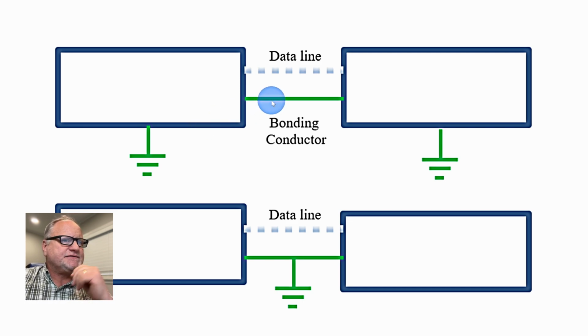It sounds great. Let's take out this bonding conductor here first. Act like this is not here. If you have this scenario, first of all, this common ground is going to be in this rack, because the things you have plugged into the house power, on that third prong of the three prongs, are going to be the common ground to the building. So you're going to have equipment attached to this ground, and the ground that's coming from the common ground is going to be attached to the equipment as well.